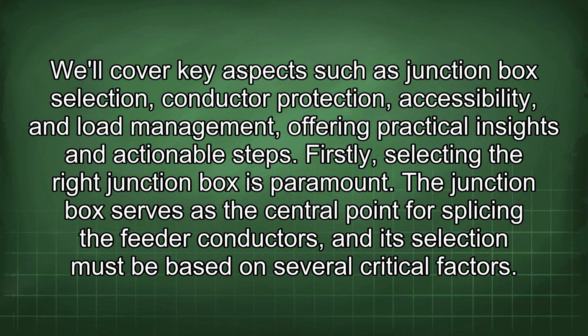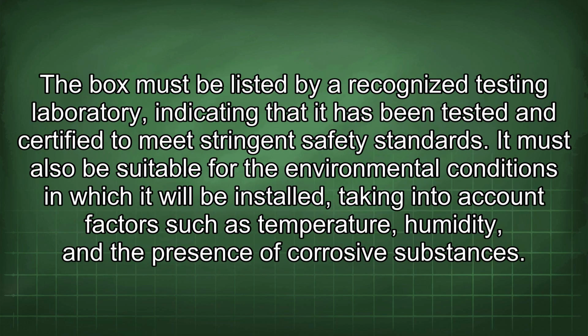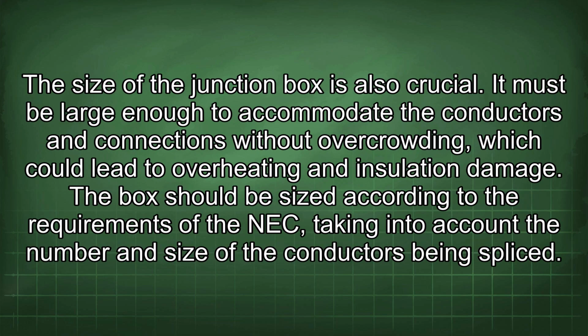The junction box serves as the central point for splicing the feeder conductors, and its selection must be based on several critical factors. The box must be listed by a recognized testing laboratory, indicating that it has been tested and certified to meet stringent safety standards. It must also be suitable for the environmental conditions in which it will be installed, taking into account factors such as temperature, humidity, and the presence of corrosive substances. The size of the junction box is also crucial. It must be large enough to accommodate the conductors and connections without overcrowding, which could lead to overheating and insulation damage. The box should be sized according to the requirements of the NEC, taking into account the number and size of the conductors being spliced.